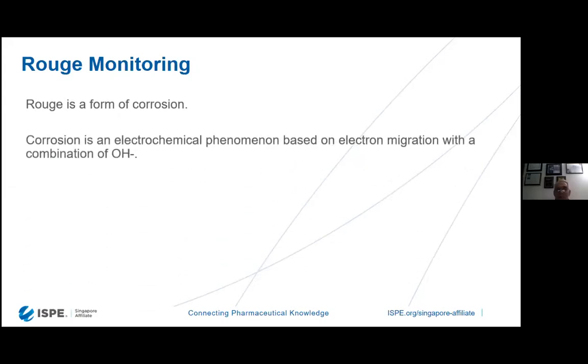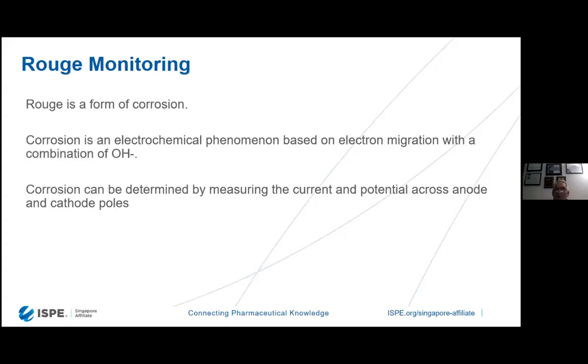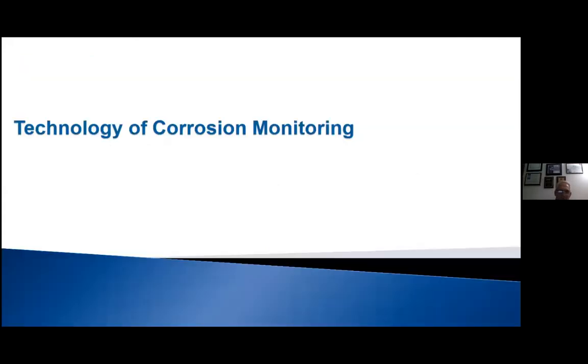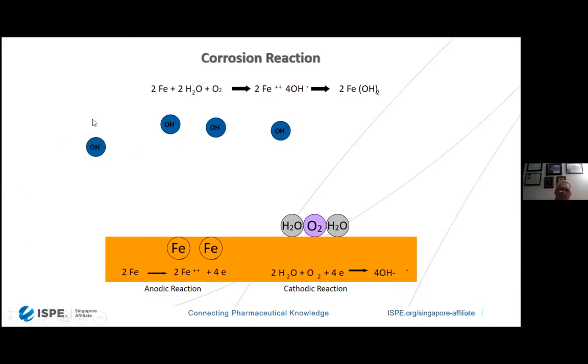Rouge is a form of corrosion, and corrosion is an electrochemical phenomenon based upon electron migration with a combination of a hydroxyl radical. Whether we're doing corrosion of organics and oxidizing them to CO2, or we're doing metal, it's the same phenomenon. Hydroxyl radicals are there in order to change the chemistry into an oxide. Corrosion, though, can be determined by measuring a current and a potential across anode and cathode poles, which is what is done with this particular instrument. So what is the technology of corrosion? Well, if you look over here at the top equation, you'll see iron plus water plus oxygen is going to yield iron ions plus hydroxyls, which formulate ferrous hydroxide. Now, what happens in metal, and 316 metal, of course, is we have an anodic reaction and a cathodic reaction.